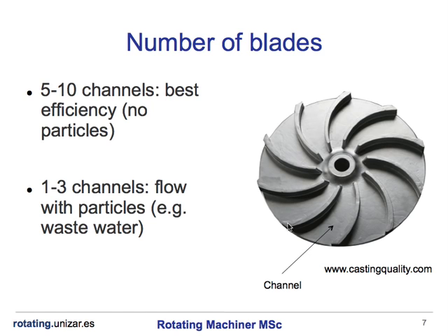If we look at the number of blades, we can find different types of impellers. The channel of an impeller is the space between two blades. The number of channels mainly depends on the desired performance and noise constraints, as well as the amount and size of solid particles in the fluid. Impellers with five to ten channels have proven to give the best efficiency and are used for fluid without solid particles.